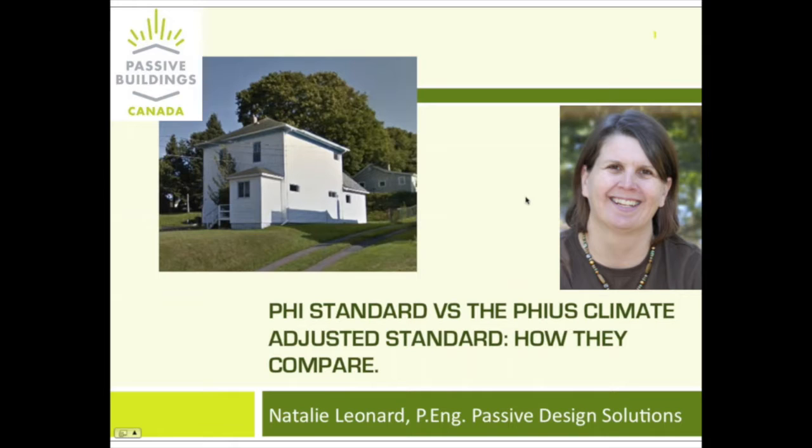So what PHIUS did is they separated that out and made an adjusted sensible recovery, and also collected the watts per CFM or CFM per watt. I can't remember which order the units go in. Those are the two numbers you need for energy modeling in both PHPP and WUFI Passive. So that sheet's available. It's publicly published on PHIUS's website under their resources.